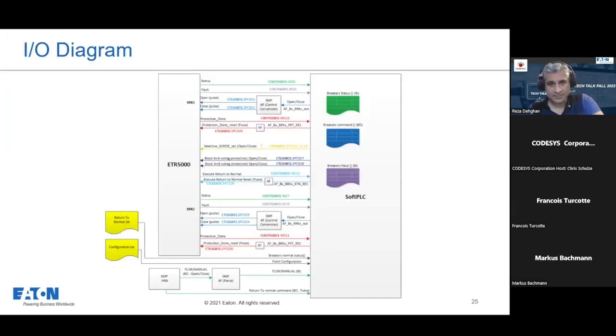Okay, code structure. So here you see this IO diagram. We don't really need to go through the details of every communication, just to get an overall look at how the system works. You see there are some communications between the ETR and the soft PLC on the right side. There are some binary input, binary output points related to each breaker, or the part of the relay that controls the breaker, and there are also some points that are related to the relay. So everything that you see in front of breaker 1 on the top and breaker 2 on the bottom, those are breaker specific points, and then everything in the middle, those are relay related points.